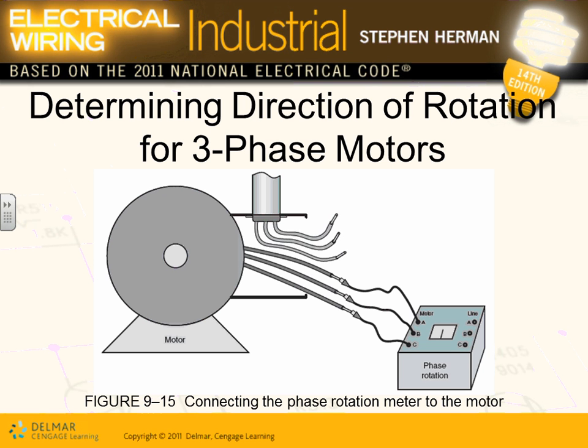This is for you, the project manager. You walk into the building and you need to connect a motor to a system. Well, if you flip two phases, what happens to the machine? Instead of exhausting air out, it starts pulling air in because you changed the rotation. So that's when rotation determination becomes a big deal. This is how it works. This is the phase rotation machine. You connect it to the machine and you spin the motor. If the motor goes in the direction that you want it to go, forward, right?